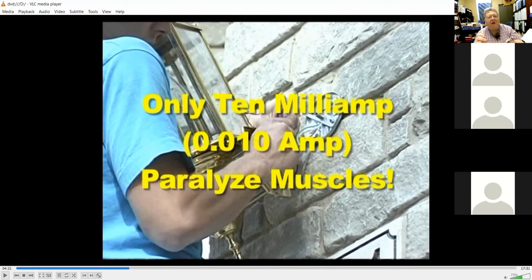So if I've got 3 amps going to the hair dryer and 2.5 amps coming back on the neutral wire, what happened to the 0.5 amp? We don't know, right? So here's what we assume. We assume that it went to ground. It had to go somewhere, and we assume it went to ground. And when that happens, it's called a ground fault. Because look, on that bare ground wire there, there's not supposed to be any current on that ground wire whatsoever, none.